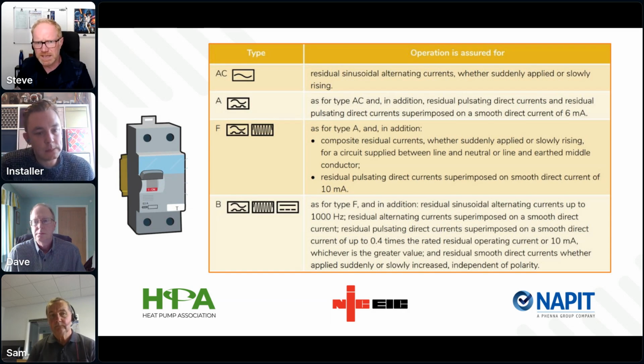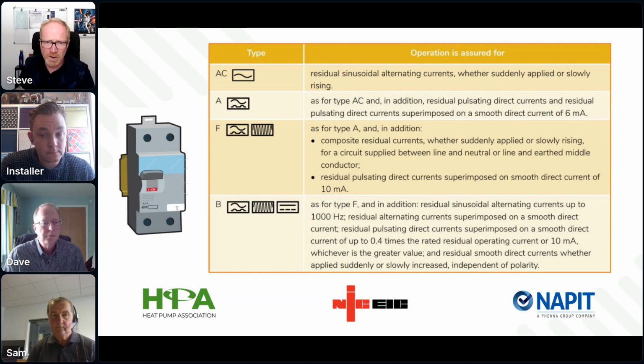Now, RCDs these days are a lot better than they used to be. You know, me and Sam remember the days when you only had to give them a glance and they'd trip. But they've improved so much now when we've got these different types that we've talked about. But at the end of the day, it's still got the potential to nuisance trip. And if that perhaps was on, let's say, a split load board, an old RCD split load board, that could cause issues for the rest of your circuits, which is not great. We've not only turned the heating off or the hot water into a property, we've also maybe got rid of sockets, lighting, and whatever else is in that domestic property.